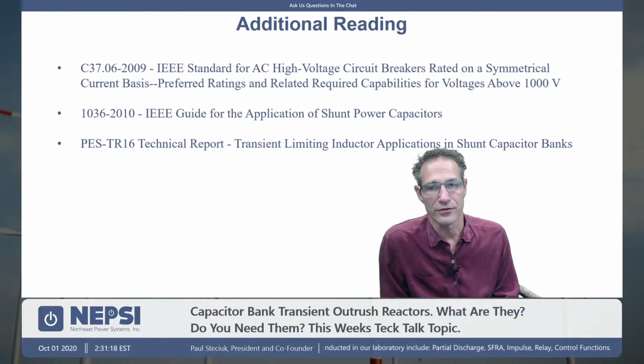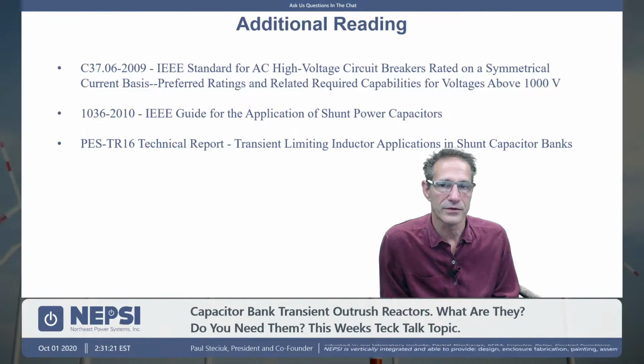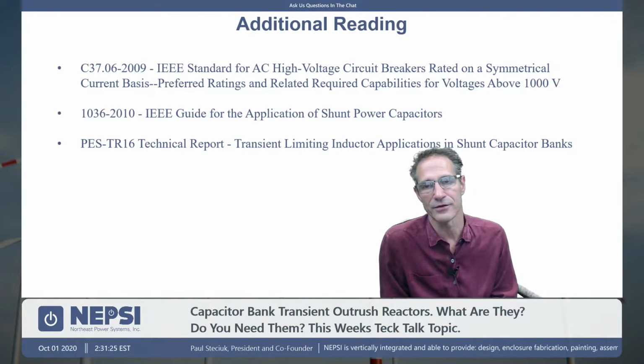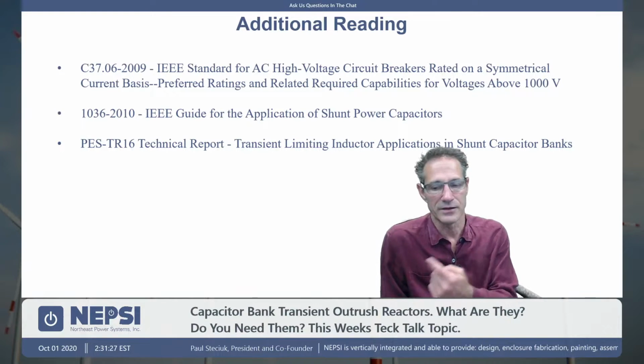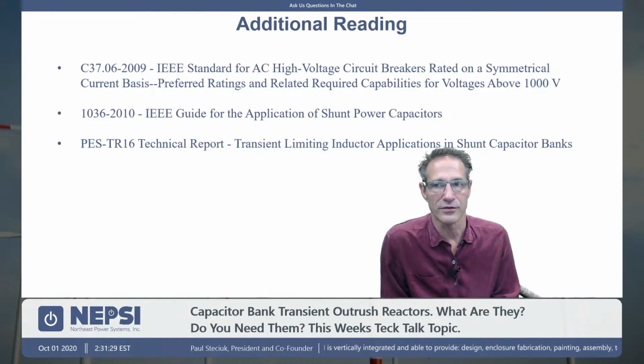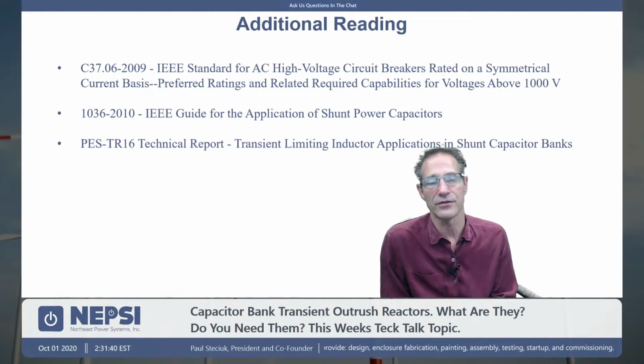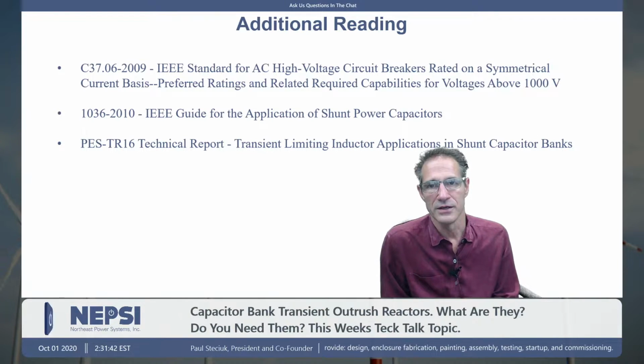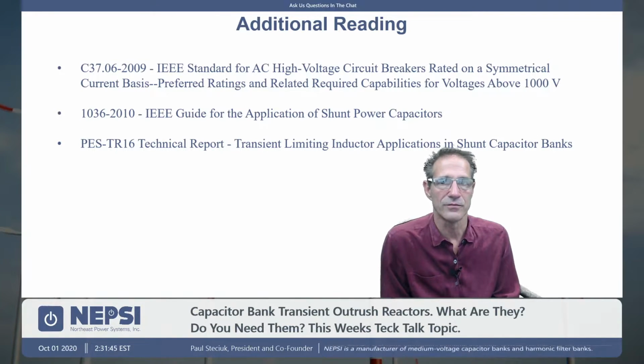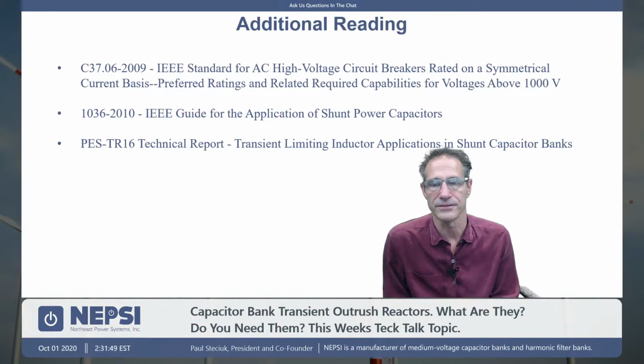And oftentimes there are fault currents. The reactors are requested to be fault current rated, and as such the epoxy impregnated type reactor that you see from companies like Trench are well suited for that application. But we do have one customer that does use iron core reactors. So again, it's a good question, and iron core reactors are possible. You have to be careful with the design. You got to make sure you specify them correctly.